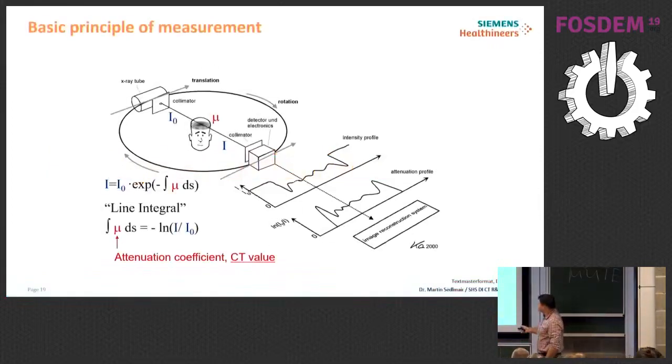So I talked about the image acquisition. This is what I call the pencil beam. So here's the X-ray source, and I talk about this very primitive example because it's easier to explain than the other examples. You scan over the patient. Here inside there is the brain, and then there is a so-called attenuation. Every tissue, bone, liver has a very different attenuation property, and this attenuation property is measured here in a single line. So you project a two-dimensional plane onto a one-dimensional line for each angle while you rotate around the patient.